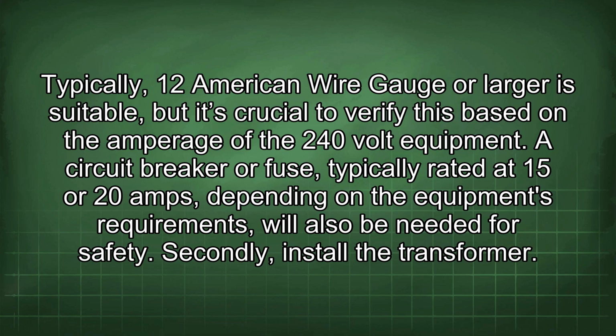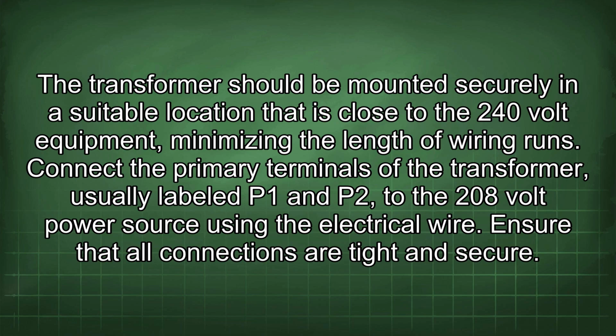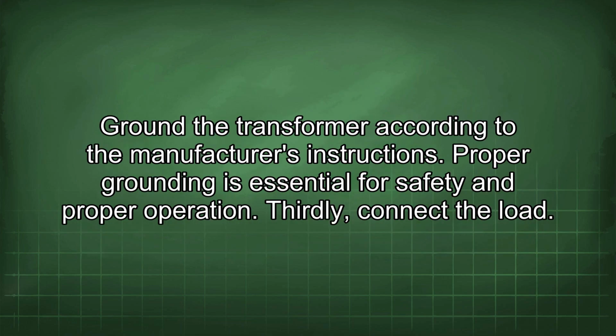Secondly, install the transformer. The transformer should be mounted securely in a suitable location that is close to the 240-volt equipment, minimizing the length of wiring runs. Connect the primary terminals of the transformer, usually labeled P1 and P2, to the 208-volt power source using the electrical wire. Ensure that all connections are tight and secure. Ground the transformer according to the manufacturer's instructions. Proper grounding is essential for safety and proper operation.